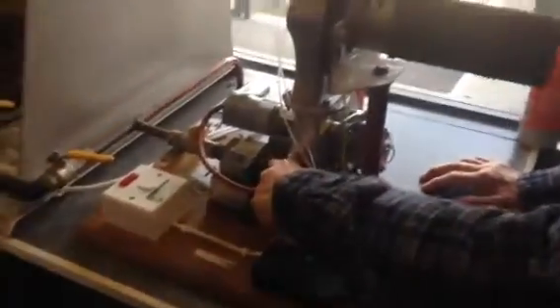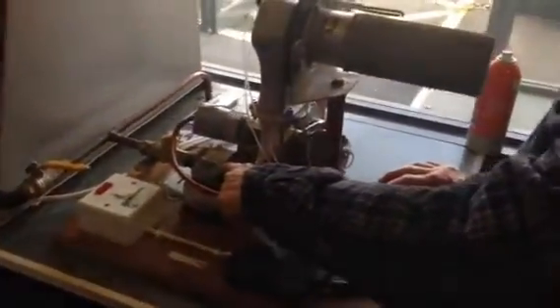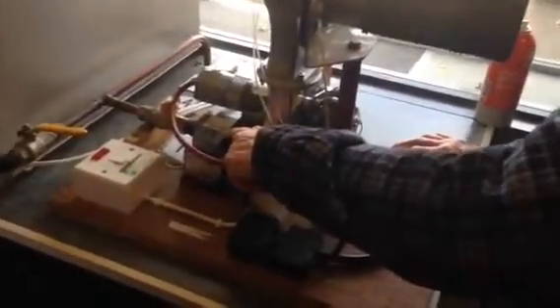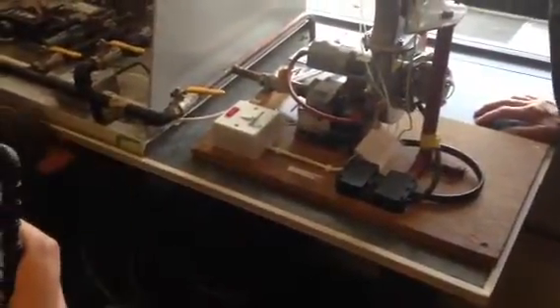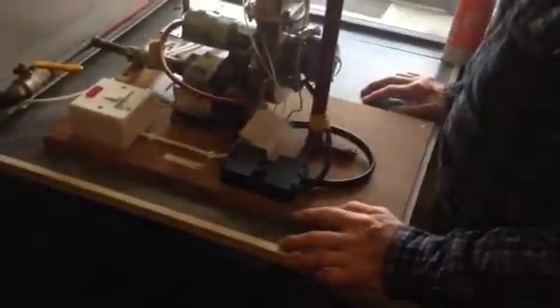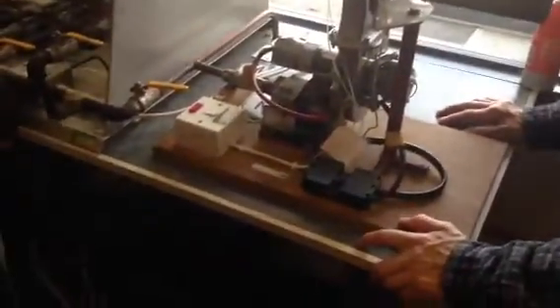So basically, if you've got 4 millibar of negative pressure caused by the fan, you'll have 4 millibar of positive gas pressure beside the diaphragm going in. That's why you will not get a burner pressure reading if you put a tube on there. You put a U-gauge on there, you'll get 0. You can get an inlet pressure, so you get a working pressure at the appliance. You won't get a burner pressure. Ideally, it should be Zippo anyway, it should be nil. If it's too far off that mark, there's probably something wrong with the settings on the valve, i.e. the offset settings. Yeah?